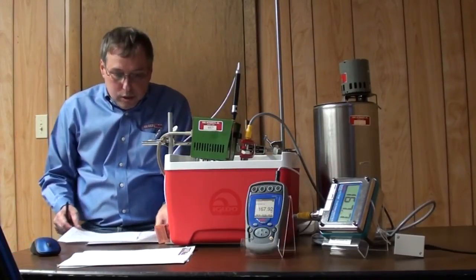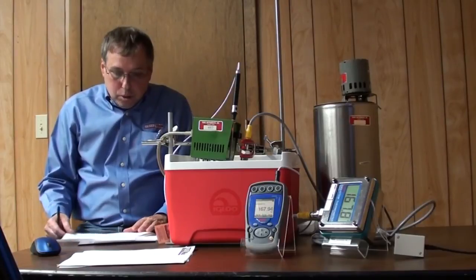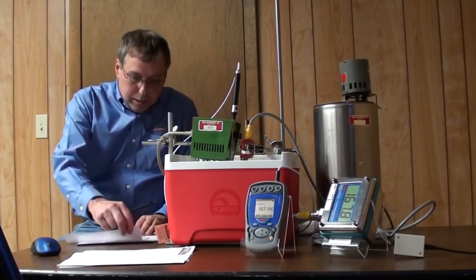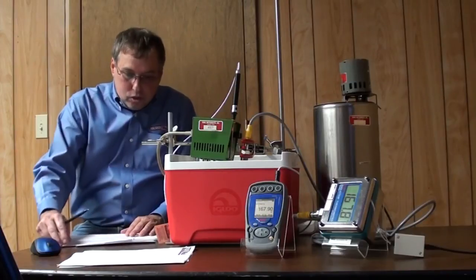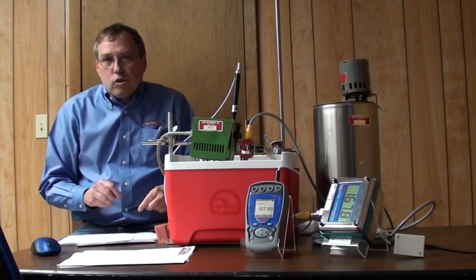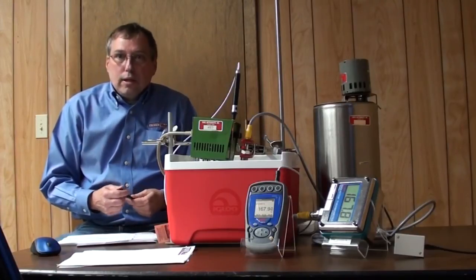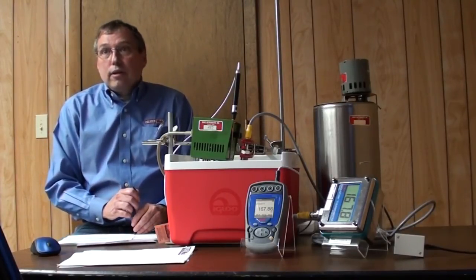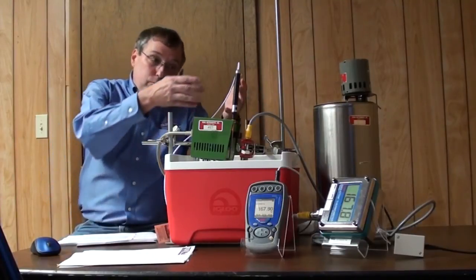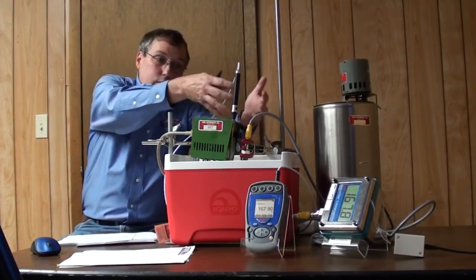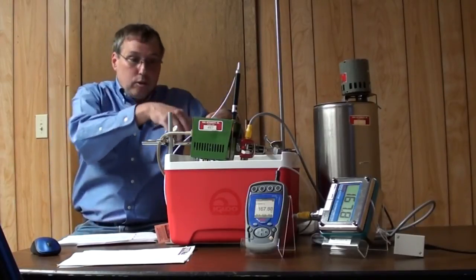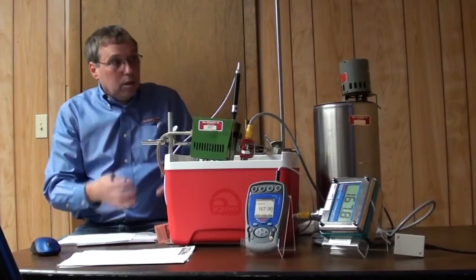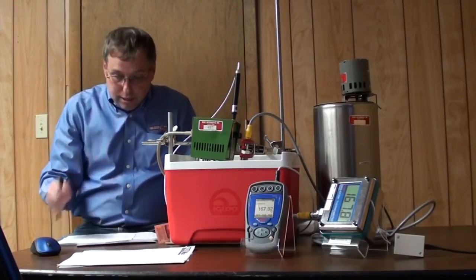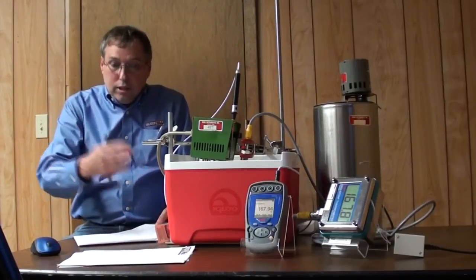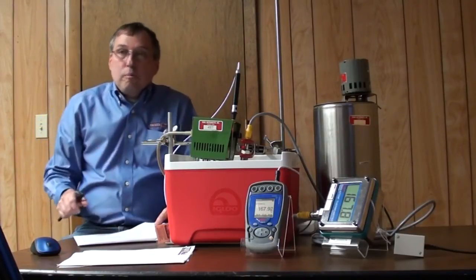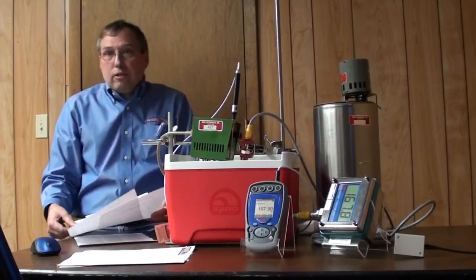Now, one of the reasons you want to use that data is that it helps you determine if a unit is still functioning properly. If you see regularly where you have 0.8 of a degree error, then that needs to raise a flag. You need to first make sure that your standard equipment's right and your setup's right, your baths are good, you're in the center of the baths where the temperature's controlled better, your fluid's good and viscous and all that. But if you continue seeing large amounts of adjustment you have to make to something, it's probably time to send that unit back to whoever manufactured it.